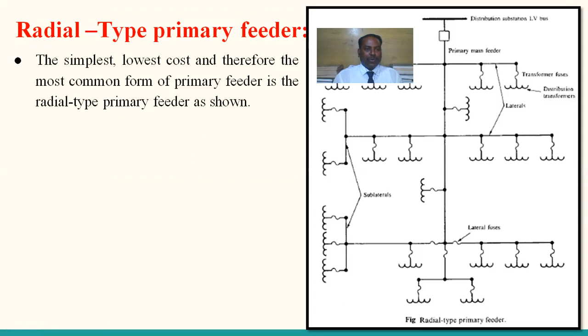The current magnitude is greatest in the circuit conductors that leave the substation. Here the current magnitude is high as it leaves the substation, and the magnitude continuously decreases towards the end of the feeder as laterals and sublaterals tap the power. So the current magnitude is high at the substation while leaving, and this magnitude continuously decreases due to the laterals and sublaterals tapping the power.